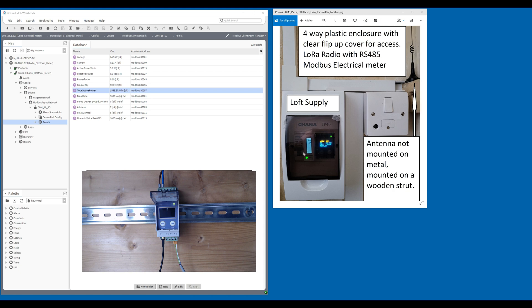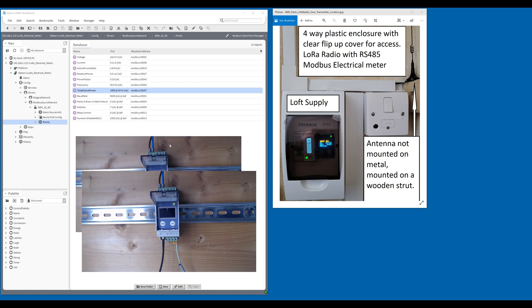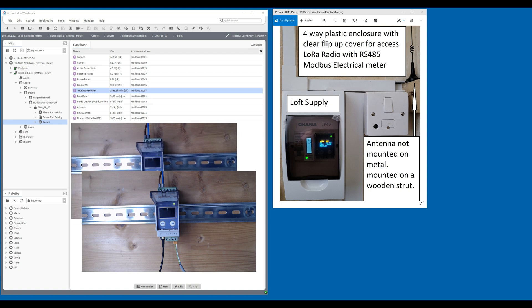This is the installation. It's a four-way plastic enclosure with clear flip-up cover for access to the circuit breakers. 16 amp MCB there. It's a single-phase Modbus electrical meter. The RS485 is going to the transmitter, which is a LoRa transmitter here. The receiver, like I said, is here, which we've got live video on. I'm going to just go through some functions while watching the live video.